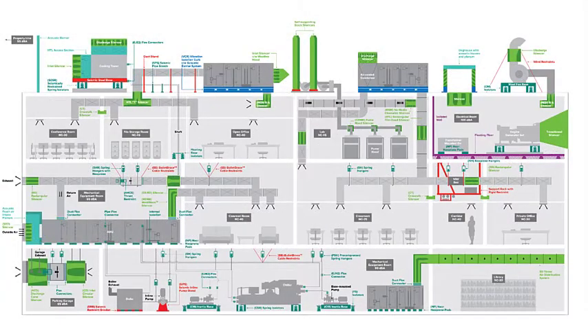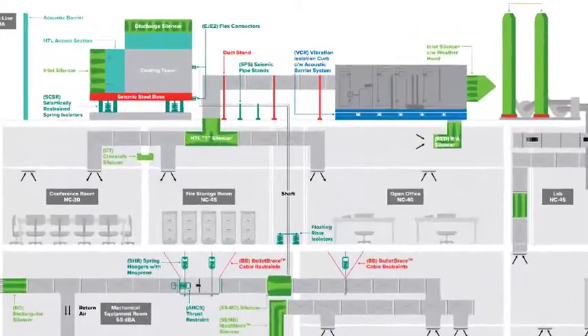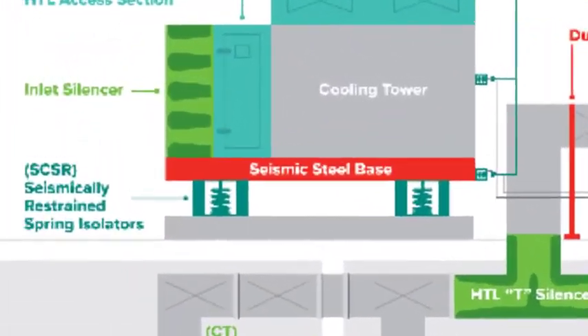Vibro-Acoustics creates noise control solutions for the HVAC industry, addressing both airborne and structure-borne transmission paths. Our vibration isolation products help mitigate equipment vibrations that could cause noise problems in buildings. In this lesson, we will look at SCSR isolators installed on a cooling tower.